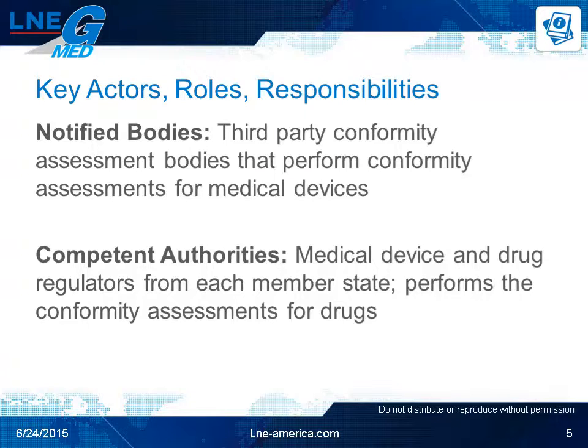Finally, the notified bodies must also get an opinion from the competent authority as part of the assessment of a product that incorporates a drug, a human blood derivative, or a tissue of animal origin that is covered by Directive 2003/32/EC. The notified body must also inform the competent authority of any significant change in its organization, just as a medical device manufacturer is assessed by a notified body. Competent authorities also assess notified bodies.